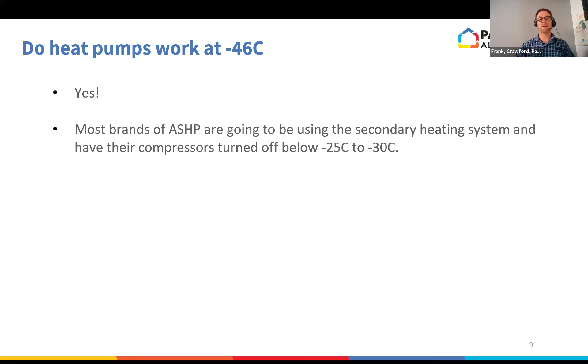Even at minus 25, my air source heat pump had no problem providing all the heating for my house, still at a fairly good coefficient of performance - better than electric resistance. For about 1 watt of energy into the compressor, it was producing probably 1.5 to 2 watts of heat. Air source heat pump technology keeps improving, so we might get that threshold lower than minus 30.